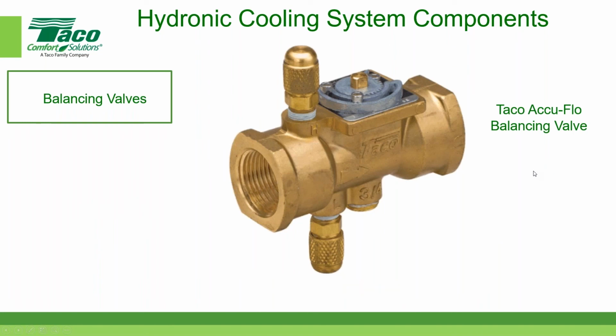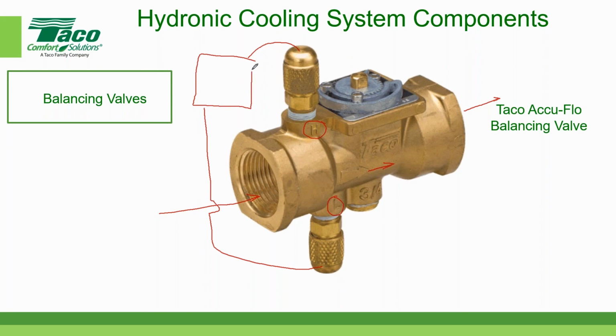We have the Taco AccuFlow, which is really cool because if you'll notice, right over here, we have the high pressure tap. Connect this to a pressure differential gauge. And this is the low pressure tap. And these are Schrader valves. The arrow indicates the flow direction. Water comes in, water goes out. You connect this one to a gauge and the other one to a gauge, and that will tell us the pressure differential across the valve.